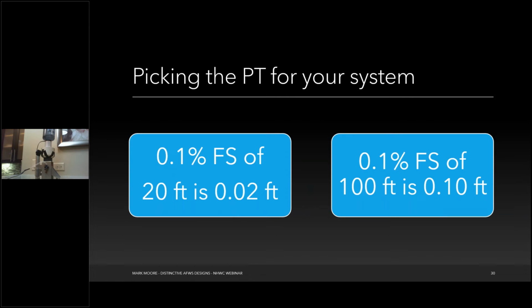0.1% full scale of 20 feet is 0.02. So if you have PTs in your system that are 20-foot range PTs, and they have 0.1% full scale error, well then, their error should be within 0.02 feet. But say you said, you know what, I want my PTs to be able to read water depth up to 100 feet because that's what my system is. Okay, well just be aware that if your full scale range is 100 feet, 0.1% of that is a tenth of a foot. So they're going to be less accurate because you have a higher range.